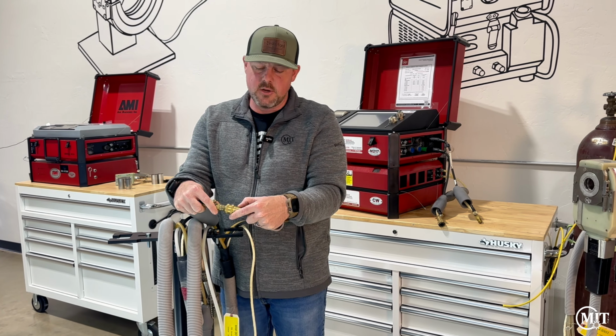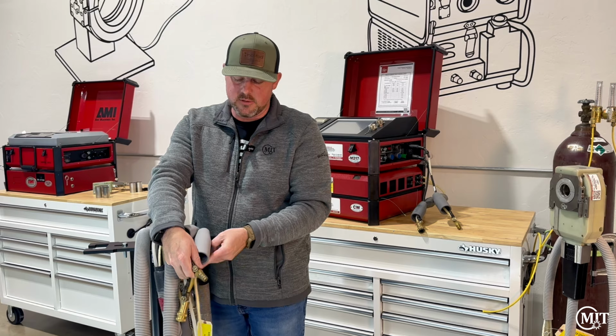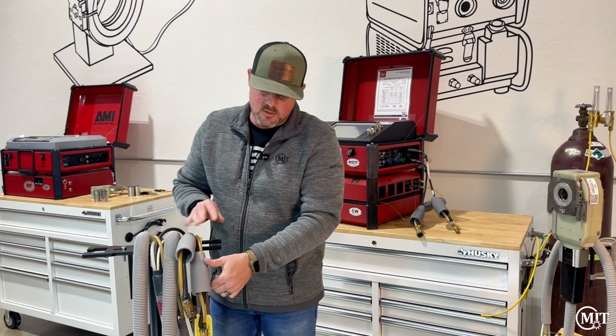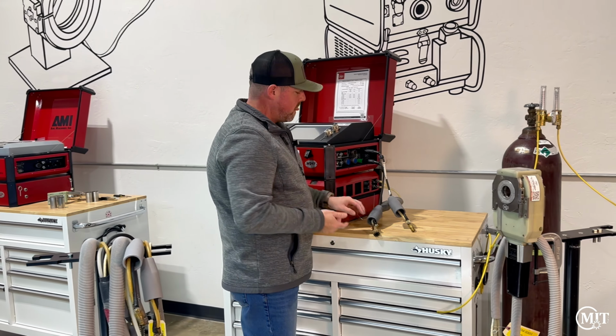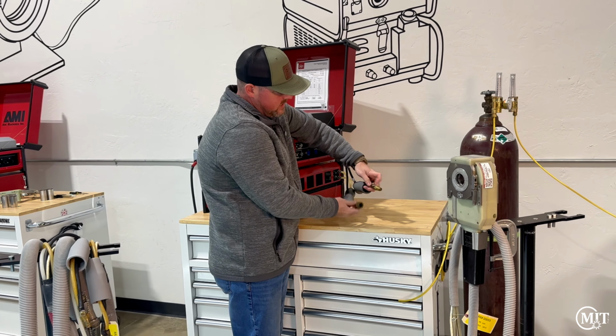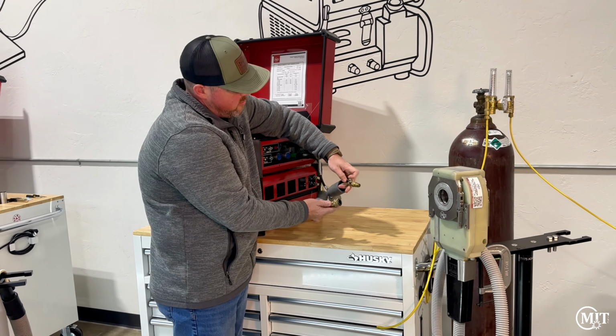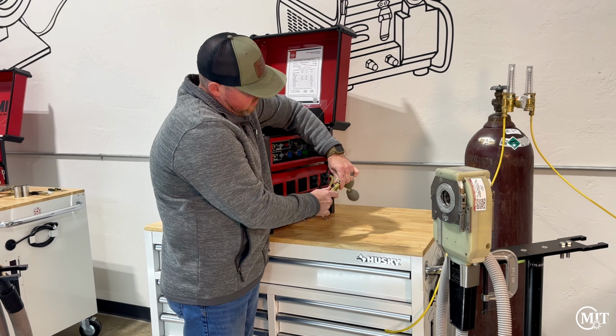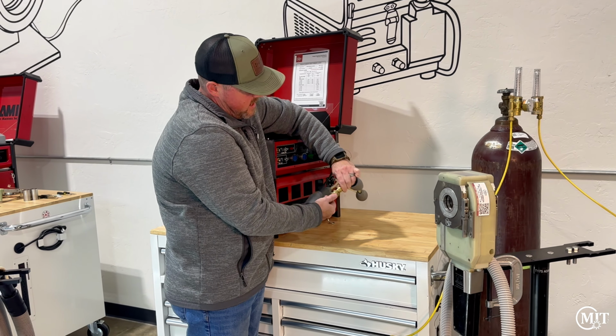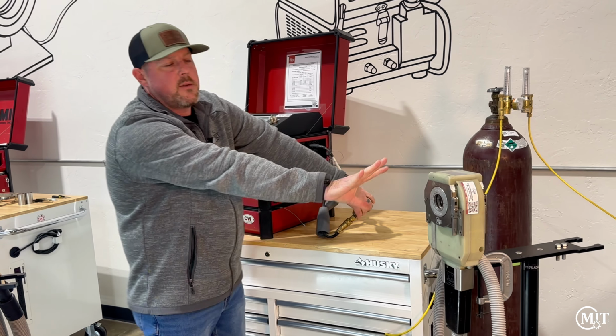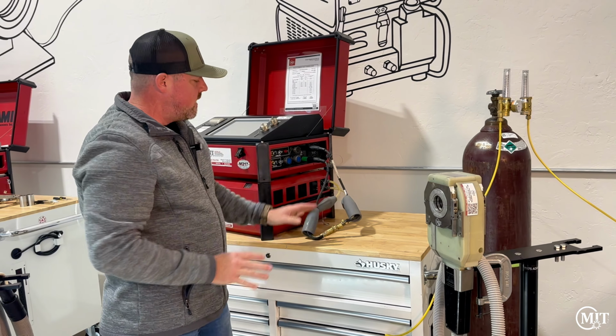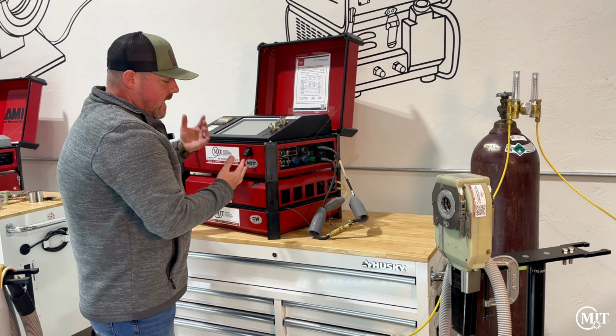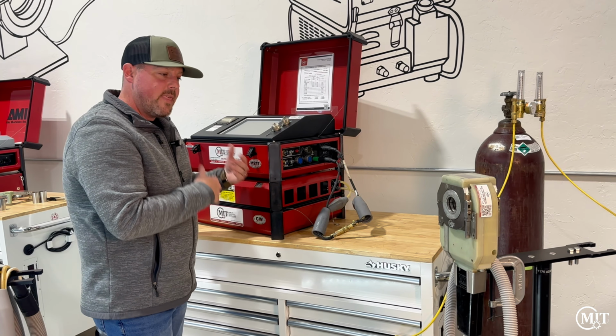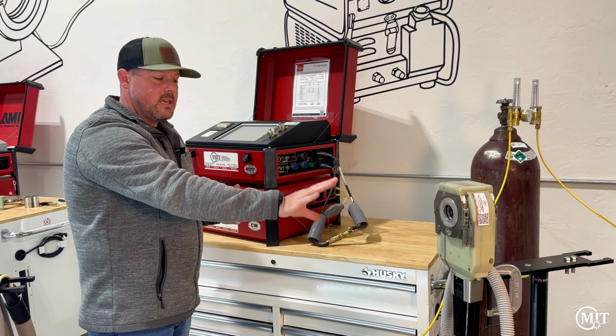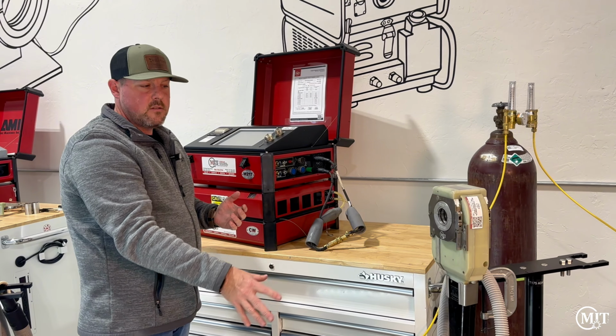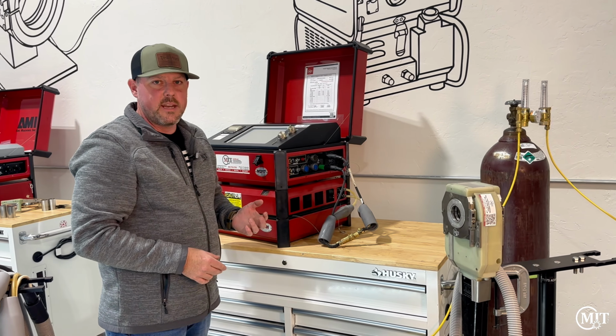I'm going to go back to the 18-inch cheater cable since that's what we have connected to our cooler. We're going to disconnect these from the weld head and put them within each other like this, just looping it at that point. So we've eliminated the weld head cable and now we're testing the adapter cable. If you have flow now, that means the clog is inside either the weld head line or the weld head itself.